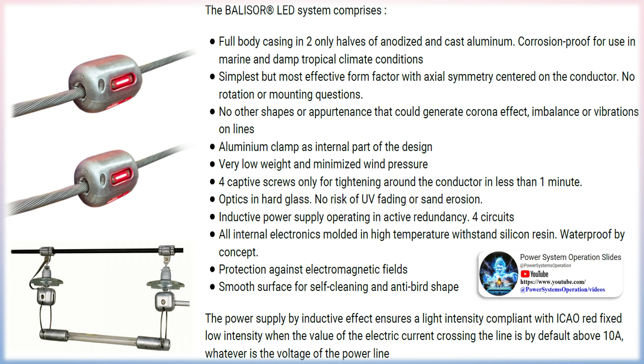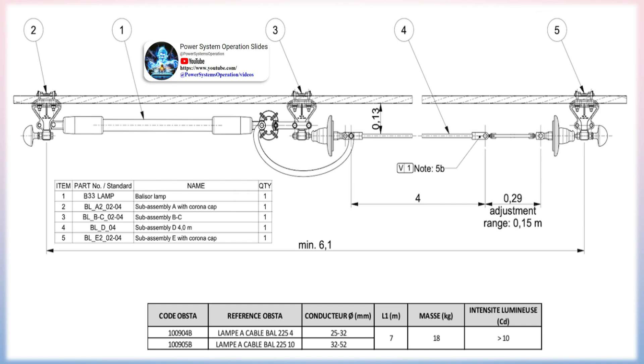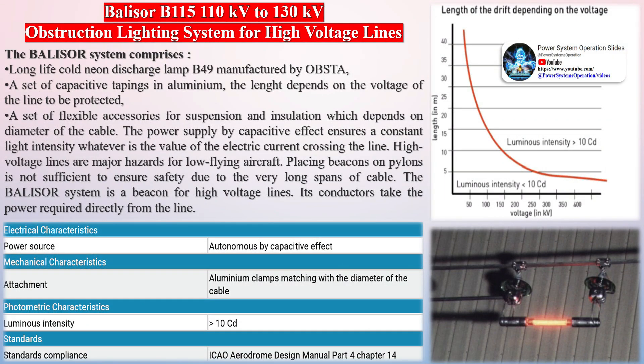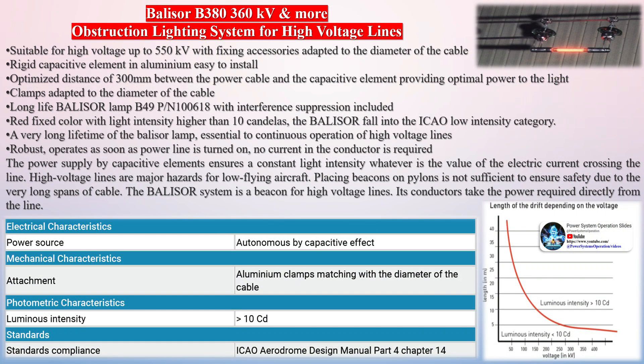Conductor marking lights are a particular type of aircraft warning lights designed for overhead power lines. They are visible at night, unlike overhead wire markers which rely on daylight. Power distribution on overhead power lines, often suspended on widely spaced masts, represents an almost invisible obstacle to low-flying aircraft, requiring the installation of warning beacons on the masts themselves. A simple and cost-effective solution is installing the marking lights directly on the wires. Nevertheless, there are significant technical difficulties to low-cost extraction of power from a distribution system which carries high voltages and wide-range AC current, and the warning system should not add the burden of additional cabling with potential serious isolation problems.